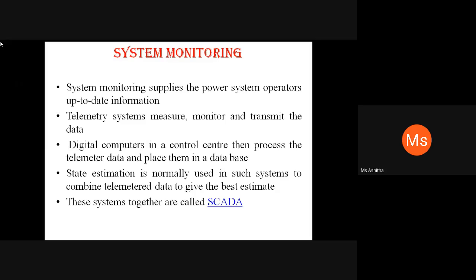The telemetry systems normally measure or monitor and transmit the data on voltages, currents and current flow, and the status of circuit breakers and switches in every substation in the transmission network. Other critical information such as frequencies, the generator output and the transformer tap position can also be telemetered. The digital computers in the control centers then process the telemetered data and place them in database form and inform the operators in case of an overload or out of limit voltage. Important data are also displayed on the large system monitors. An alarm or warning may be given if required.